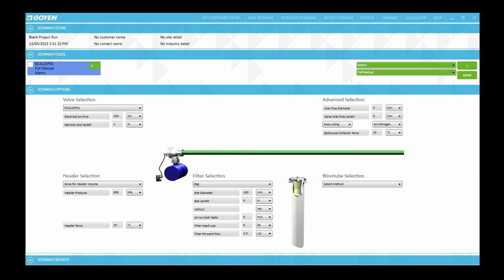The next parameter that will need to be determined is the air to cloth ratio. Now this is the ratio of the filter flow rate to the filter area. And for this example for a coal-fired boiler a typical value will include 0.025 metres per second. And then we also have the units of feet per second, feet per minute or metres per minute.